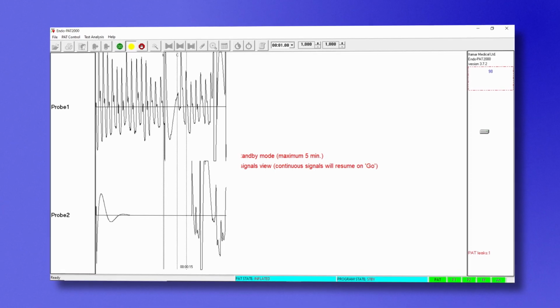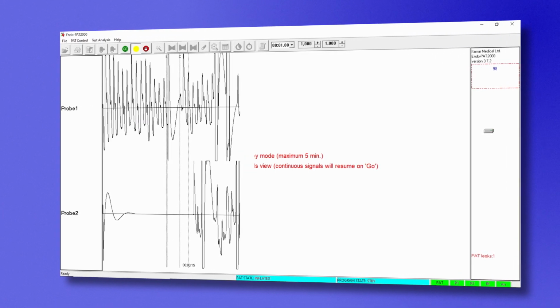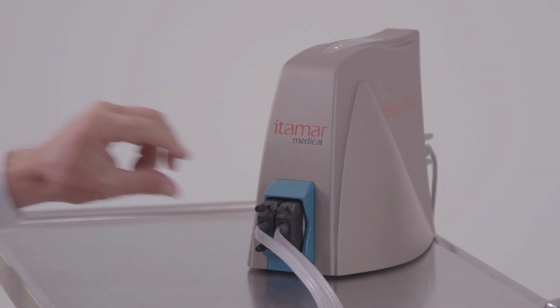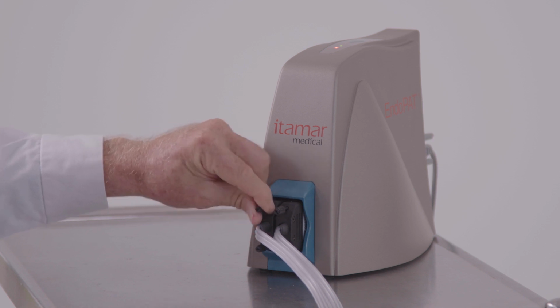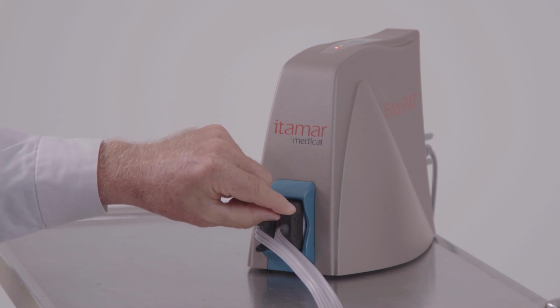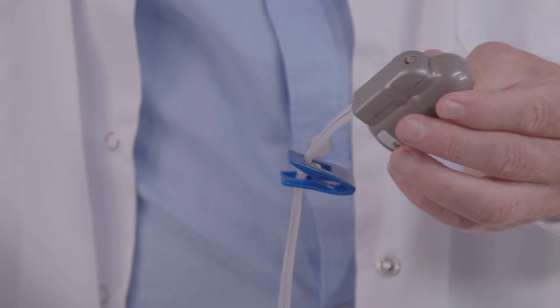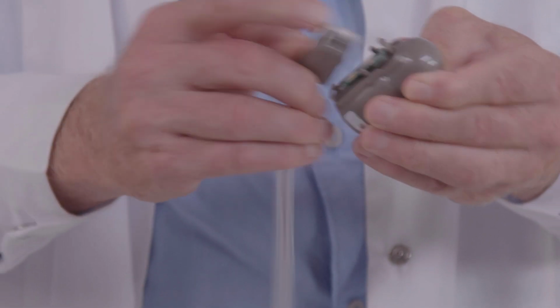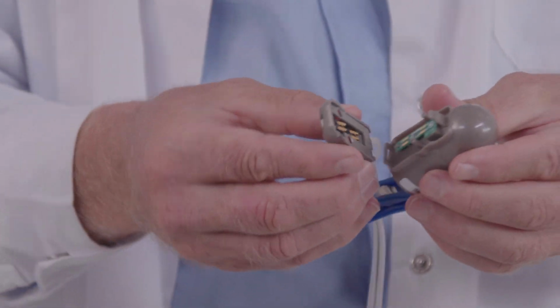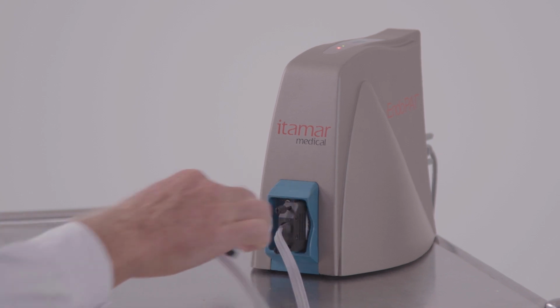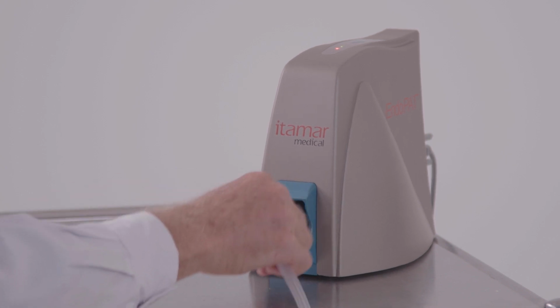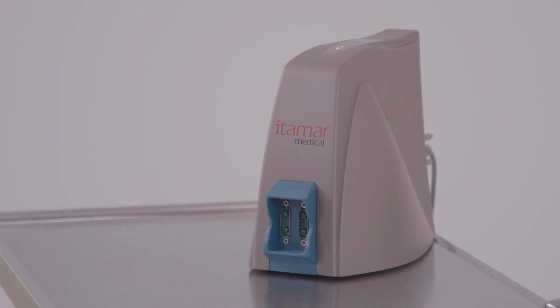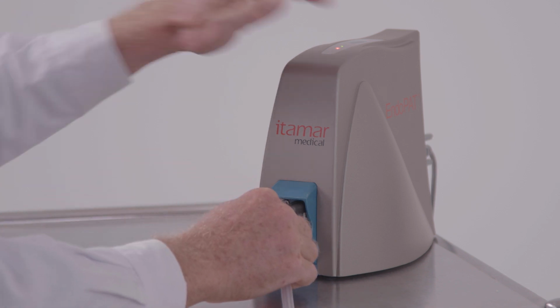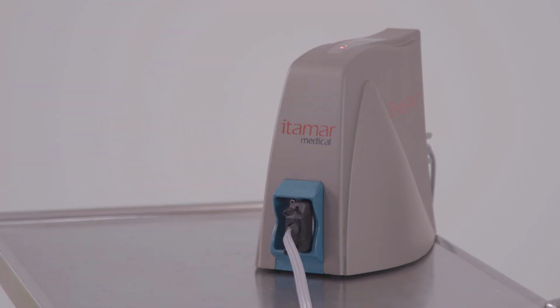If leaks continue and occur more than 2 leaks a minute, try the following steps. Fasten tubes tightly to the device. Check if the connector is secured to the probe. Deflate and replace the probe. Reinflate, resume standby. Deflate and replace the tube. Reinflate and resume standby. Signals data is not being recorded during this stage, and probes are not considered used.